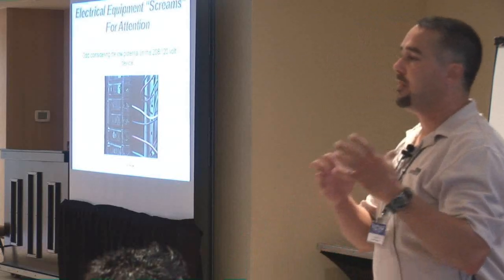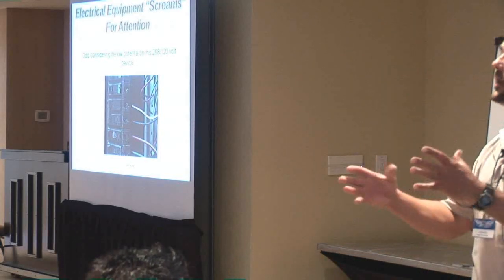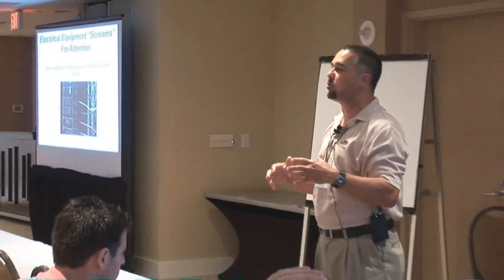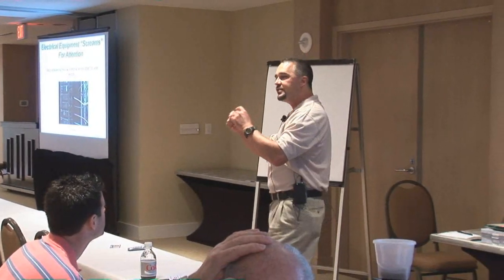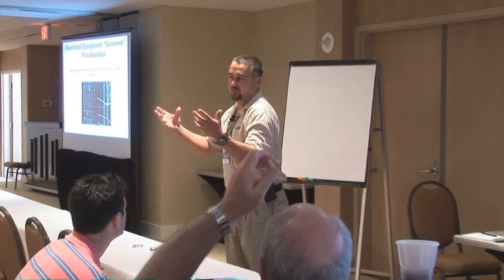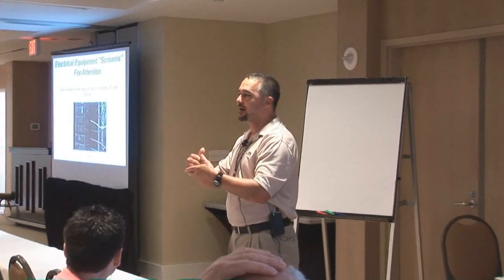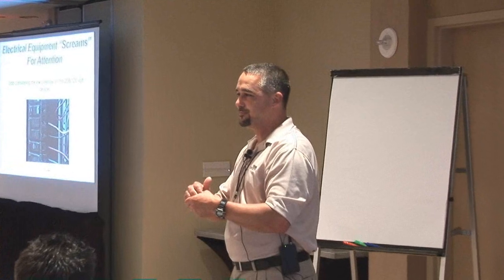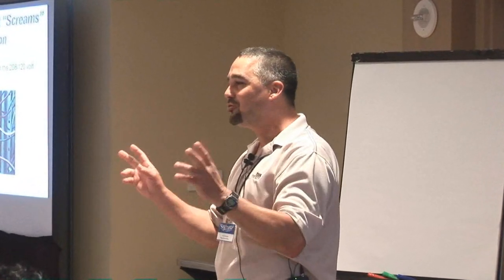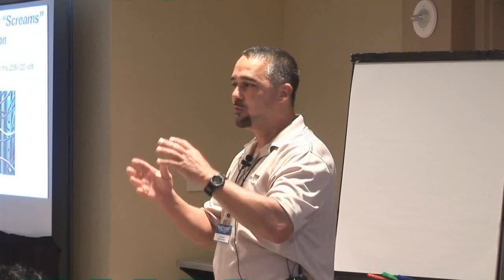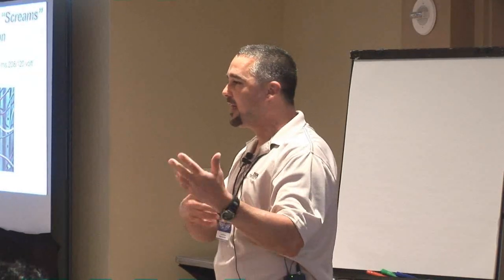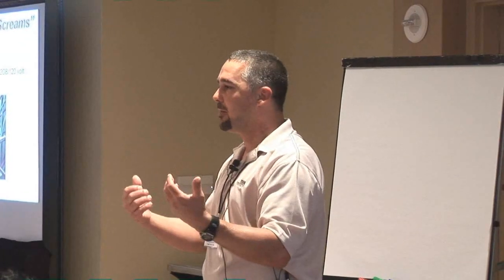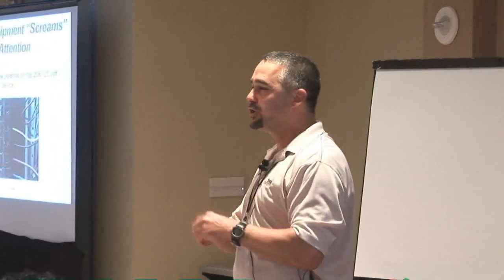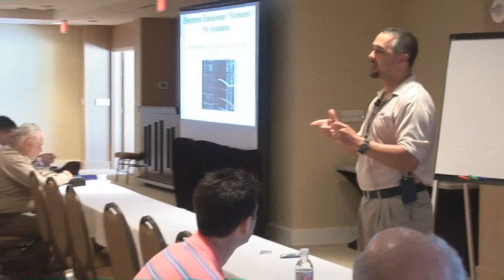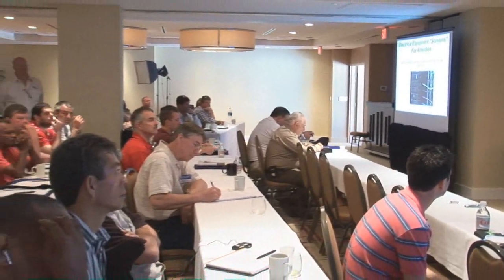Yes. Actually, on this type of equipment, we would not even open it up without doing an airborne scan. But on a hermetically sealed molded case circuit breaker, typically even if something's going on inside, you should not have airborne emissions. I have run across it once or twice in the past where you did, but they were so degraded and the intensity level was so high it became airborne in that fashion. Normally I would not ask the technicians to go down to this level using the contact module, but for training purposes we did.